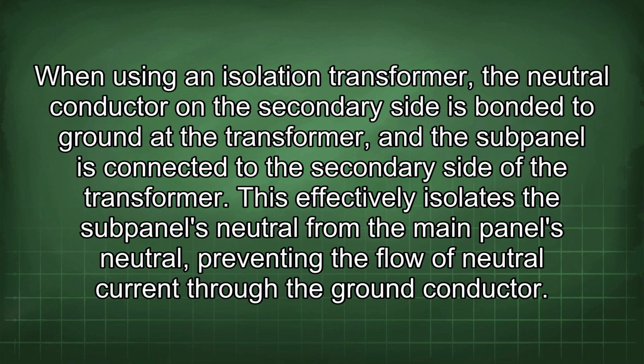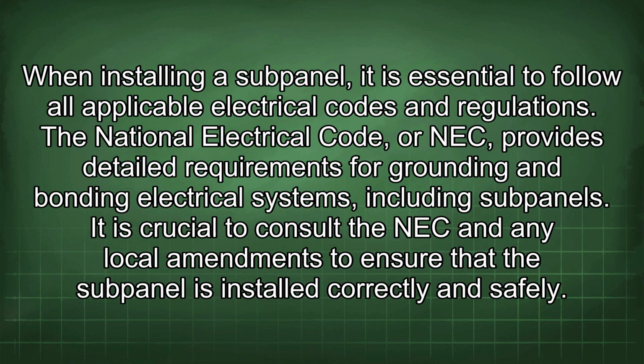When using an isolation transformer, the neutral conductor on the secondary side is bonded to ground at the transformer, and the subpanel is connected to the secondary side of the transformer. This effectively isolates the subpanel's neutral from the main panel's neutral, preventing the flow of neutral current through the ground conductor. When installing a subpanel, it is essential to follow all applicable electrical codes and regulations. The National Electrical Code, or NEC, provides detailed requirements for grounding and bonding electrical systems, including subpanels. It is crucial to consult the NEC and any local amendments to ensure that the subpanel is installed correctly and safely.